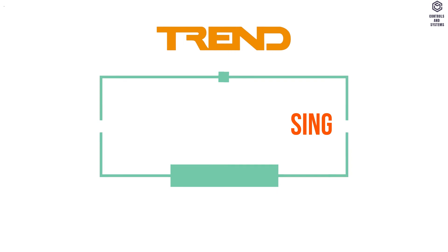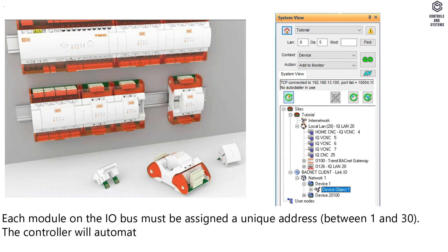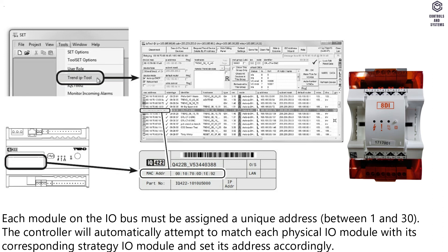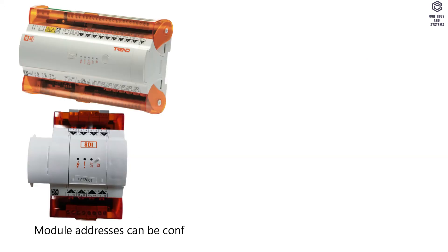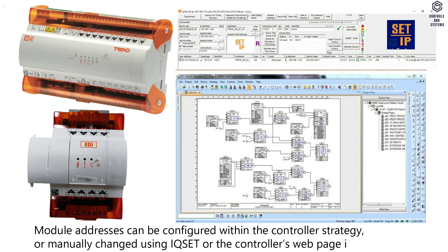I/O module addressing: each module on the I/O bus must be assigned a unique address between 1 and 30. The controller will automatically attempt to match each physical I/O module with its corresponding strategy I/O module and set its address accordingly. Module addresses can be configured within the controller strategy, or manually changed using IQSET or the controller's web page interface.